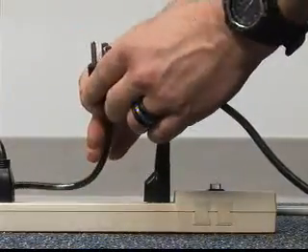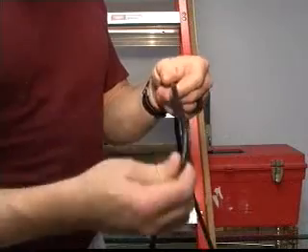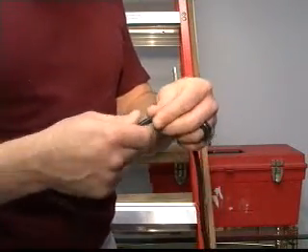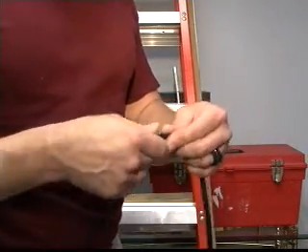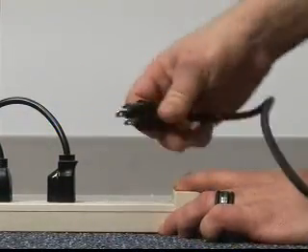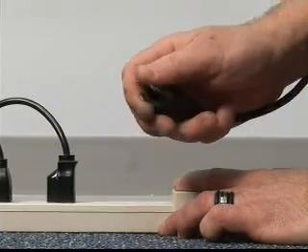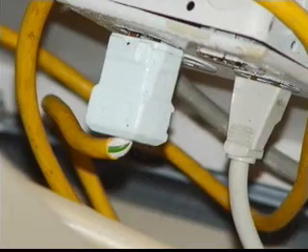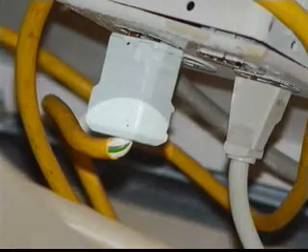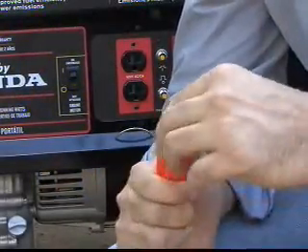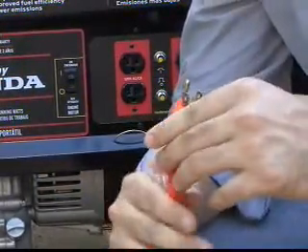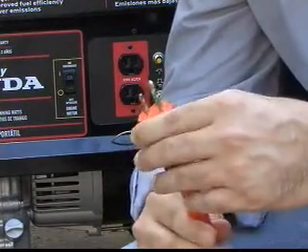It should be inspected periodically to make sure the ground wire inside the system is properly connected, and each person using the equipment should always inspect to make sure the prong is intact and that all wiring is in good condition. Wiring or cables that are cracked, frayed, cut, or damaged must be replaced. Inspect the connections to your equipment. If you notice any loose or worn parts, report it so it can be corrected.